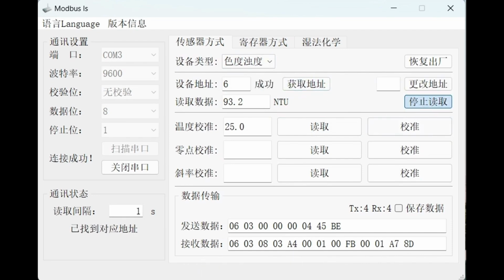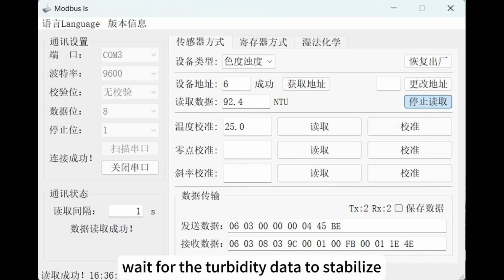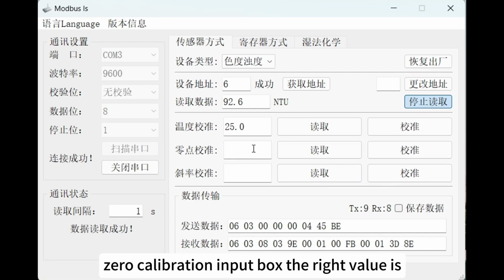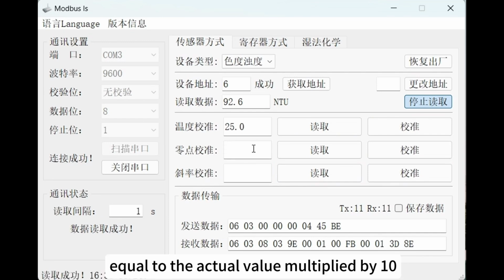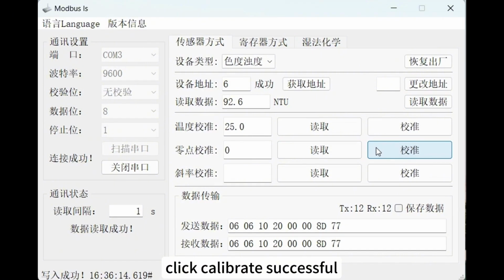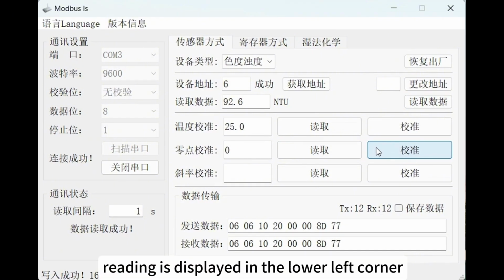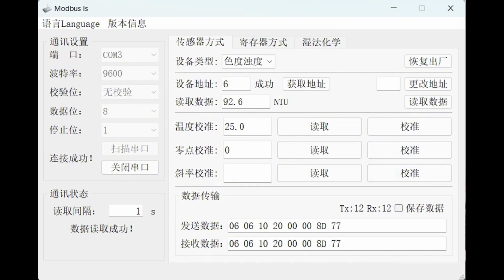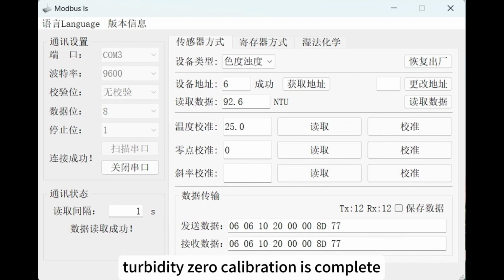Read the data. Wait for the turbidity data to stabilize. Then enter the right value in the zero calibration input box. The right value is equal to the actual value multiplied by 10. Click Calibrate. Successful reading is displayed in the lower left corner. Turbidity zero calibration is complete.